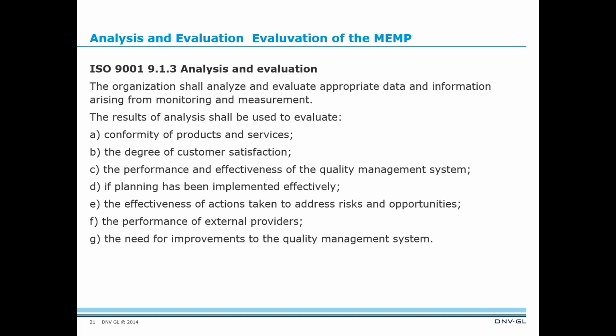This is where you look at your policy improvement indicator and you say, these are 3 areas or 1 area that we had a problem with. We didn't make the mark. For example, which biomed shop actually had 100% PM completions during COVID? I know we didn't. We tried, but when the equipment's in use all the time, you can't go in there and do a PM. But there is a form you fill out, and there is a process that we do.